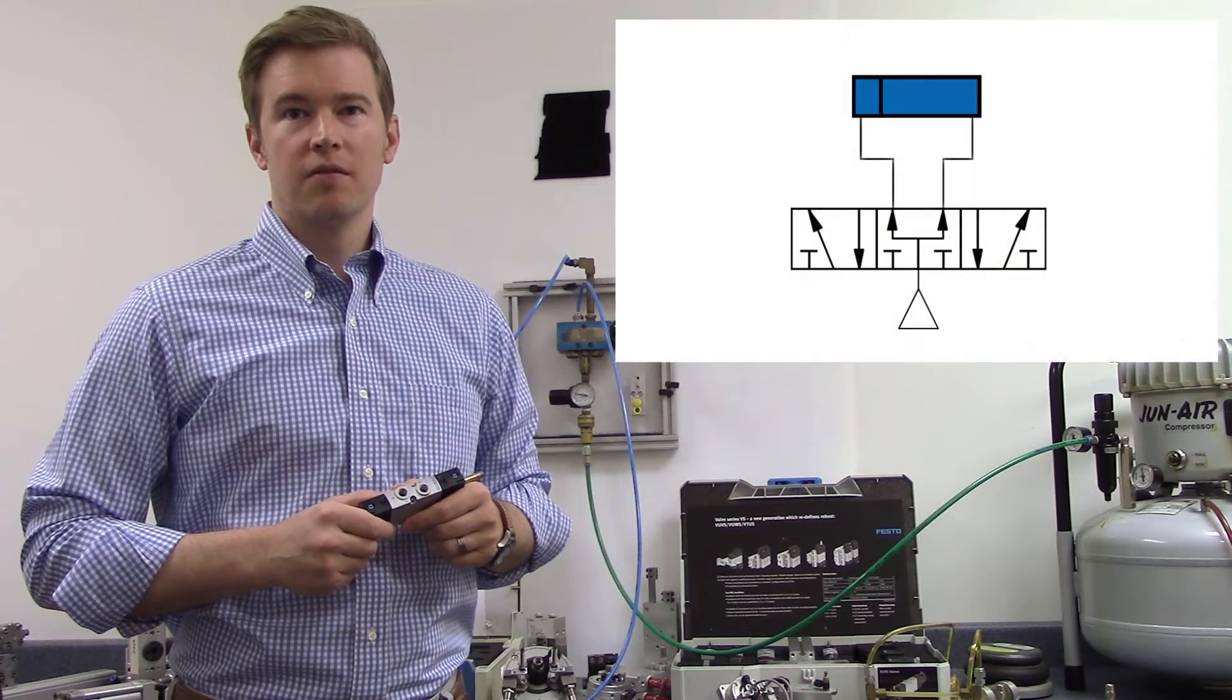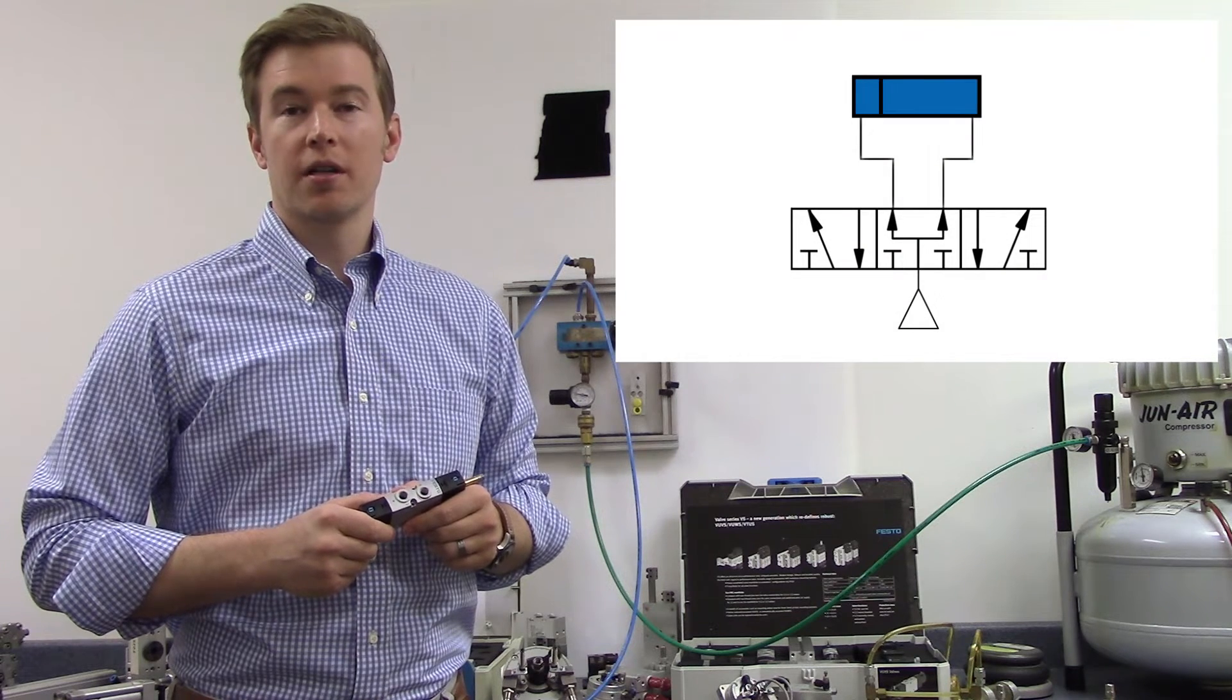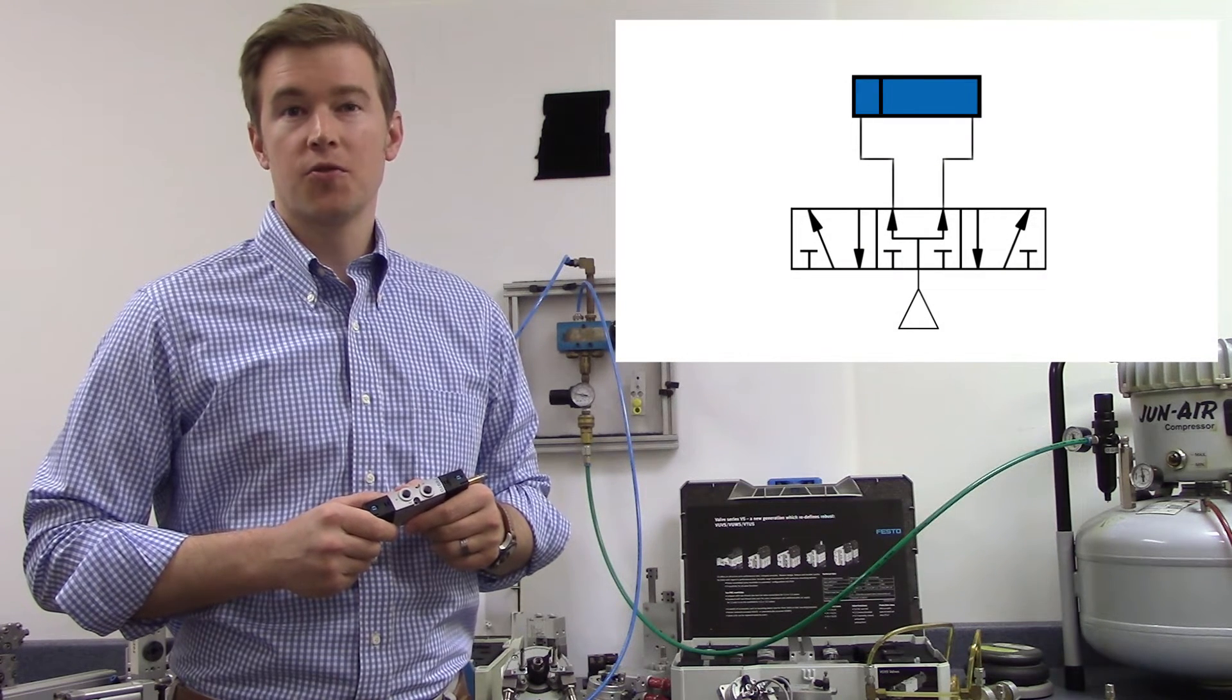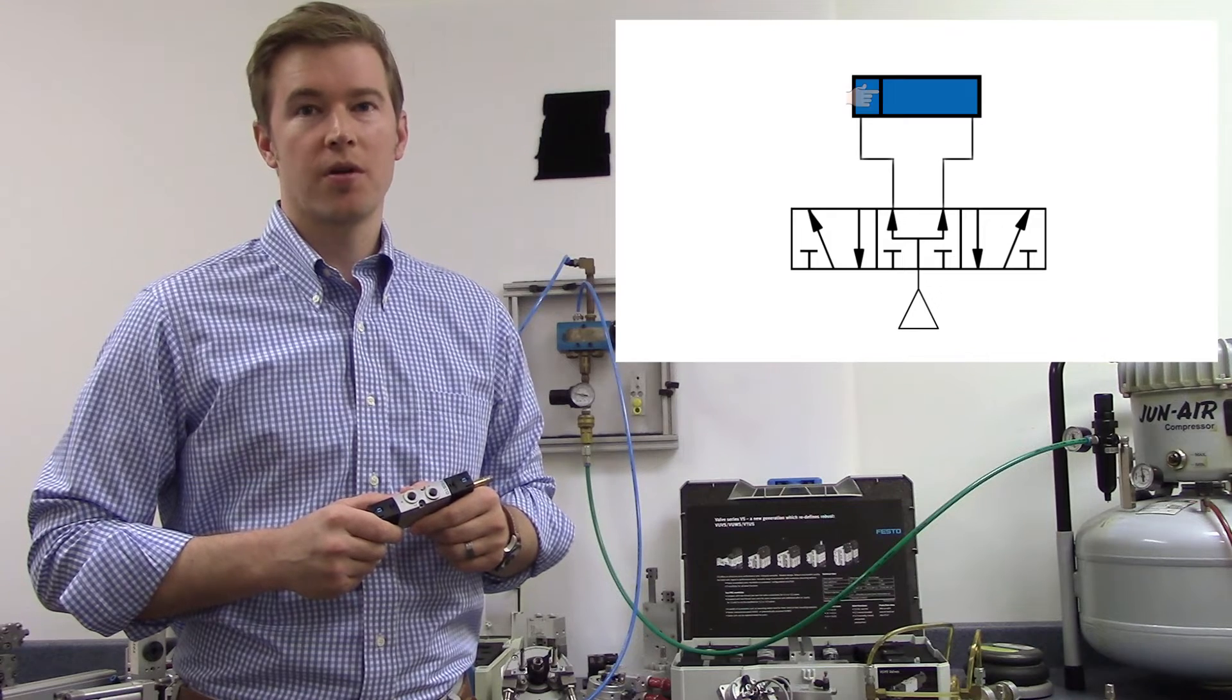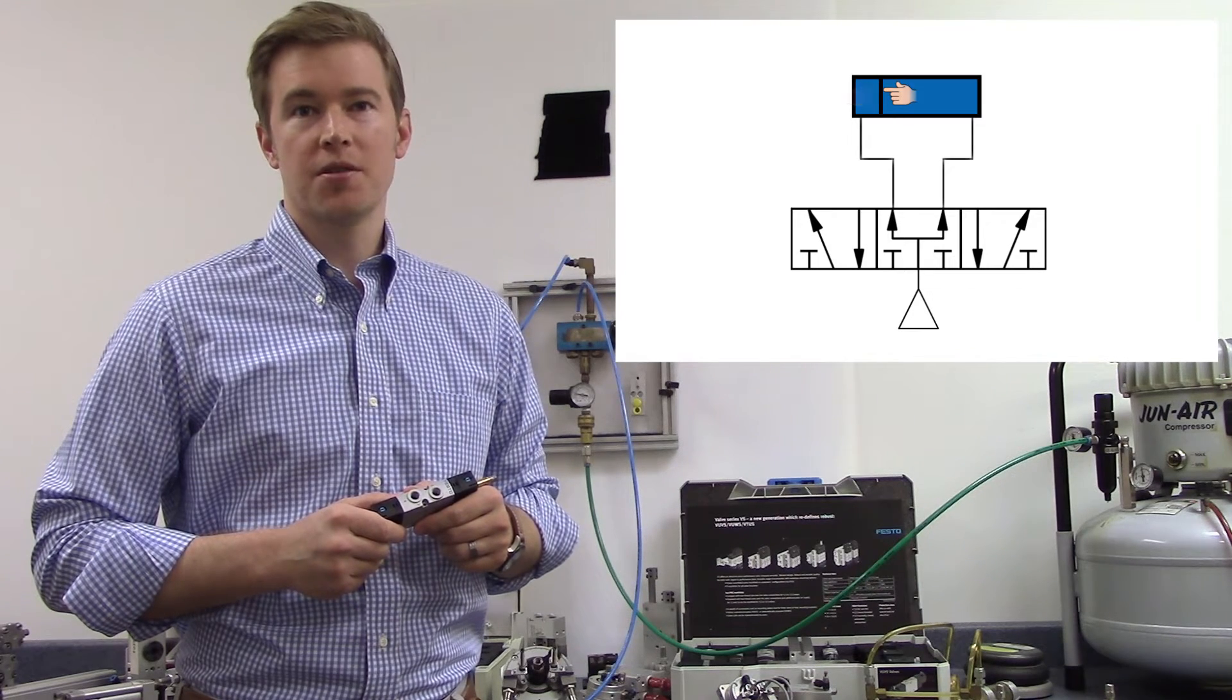In a middle position pressurized valve, only the supply port and the working lines are left open. This is useful for holding rodless or rotary actuators in place as both sides of the piston or vane remain pressurized.